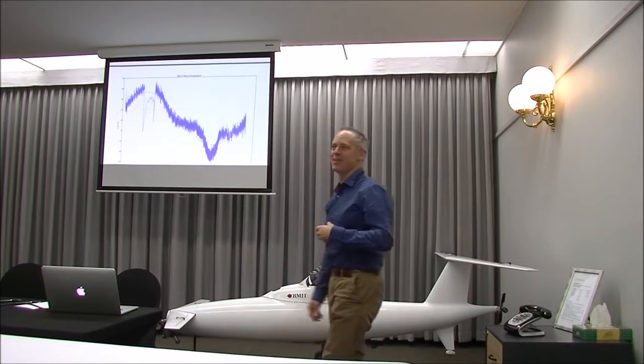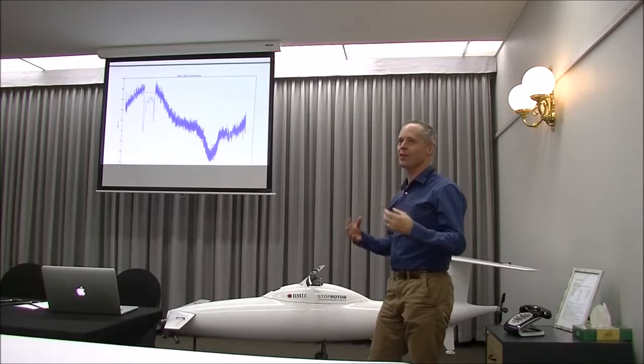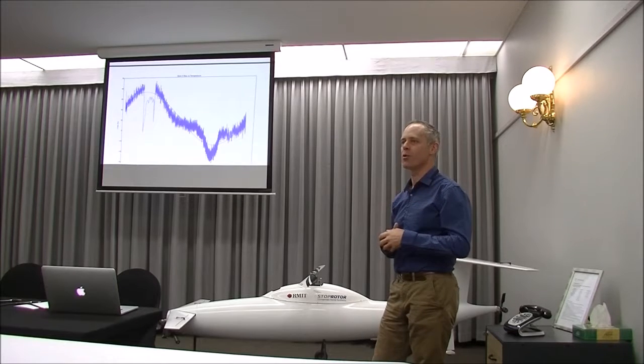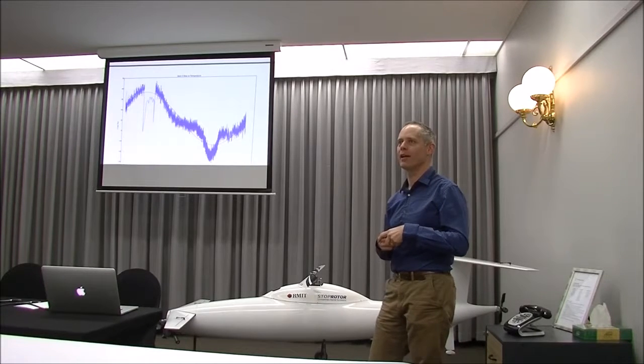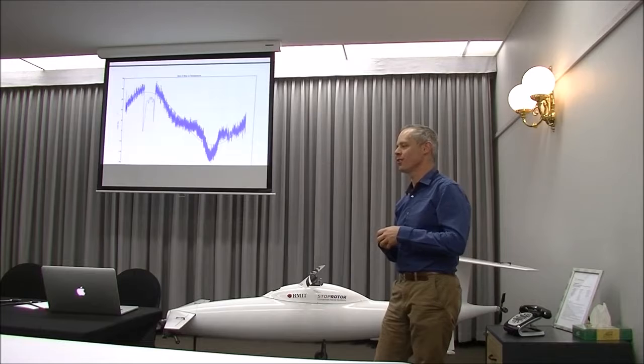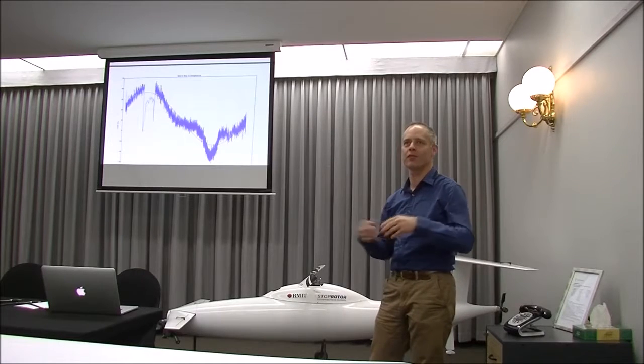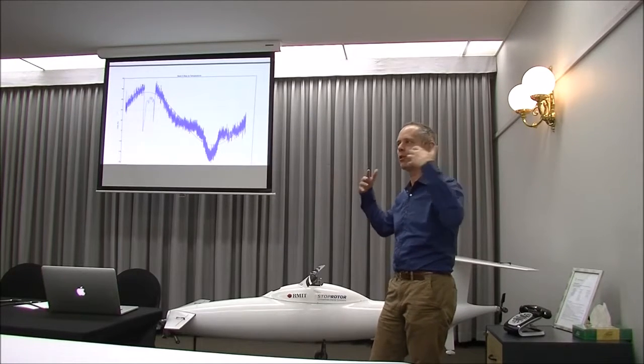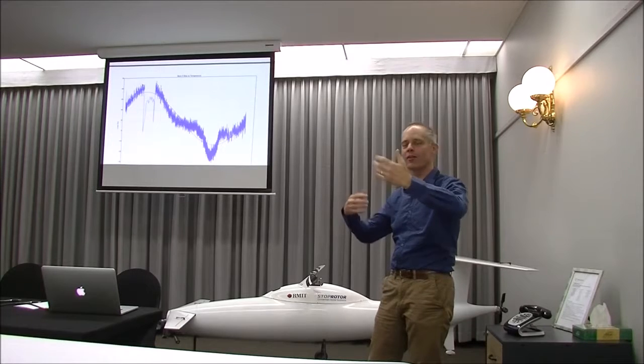So yeah, this is the problem. Barometer is probably the hardest sensor to do a thermal calibration with, because as soon as you have a chamber where you're blowing air in or blowing air out, it's going to vary. If it's in a house and you've got wind, or in a building and you've got wind loading on the building, it can pressurise, or otherwise...